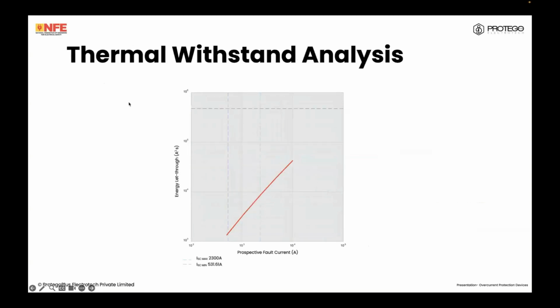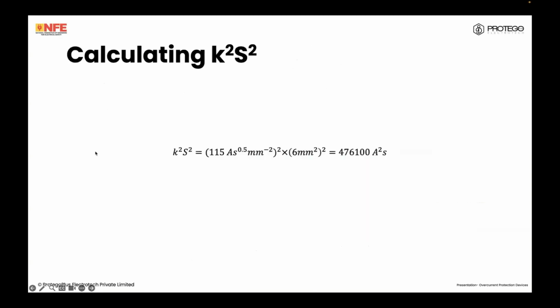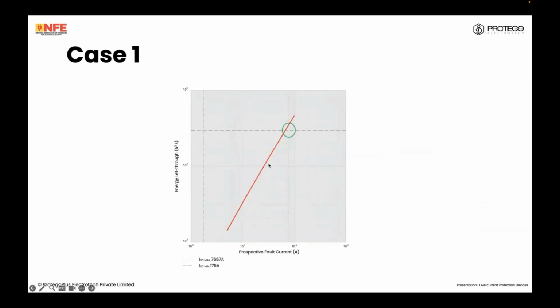Case number 1, where thermal withstand analysis will fail. When you do these calculations, you will realize that your cable is not sized properly or your breaker is rather oversized. For maximum prospective fault currents, which are faults that occur closest to the breaker, the value of let through energy released by the circuit breaker is greater than what the cable can withstand.